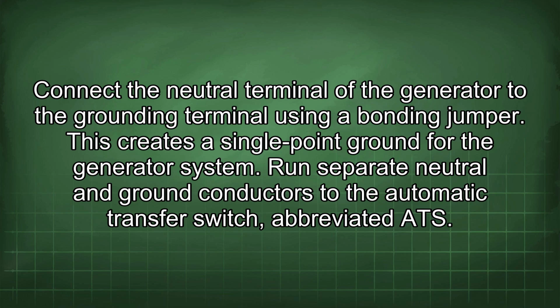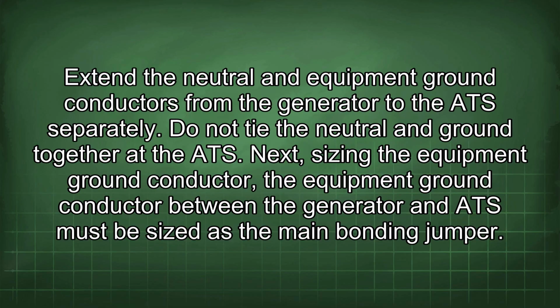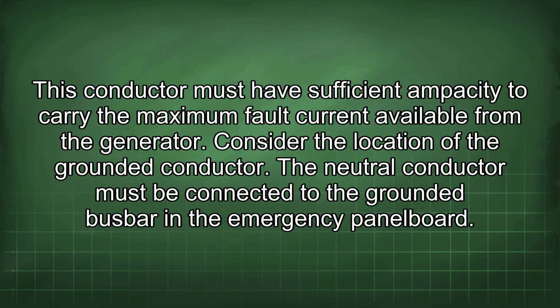Run separate neutral and ground conductors to the automatic transfer switch, abbreviated ATS. Extend the neutral and equipment ground conductors from the generator to the ATS separately. Do not tie the neutral and ground together at the ATS. Next, sizing the equipment ground conductor. The equipment ground conductor between the generator and ATS must be sized as the main bonding jumper. This conductor must have sufficient ampacity to carry the maximum fault current available from the generator.